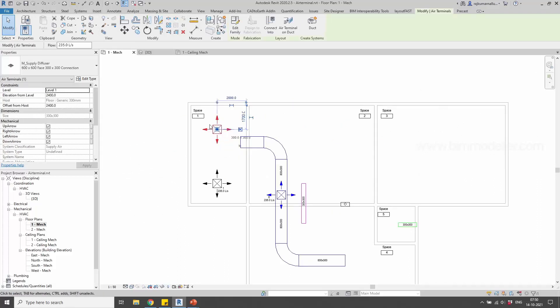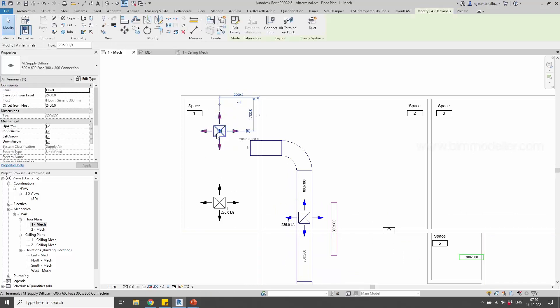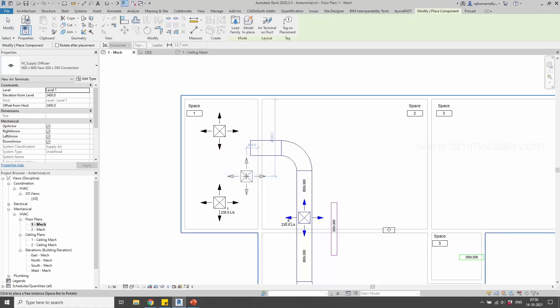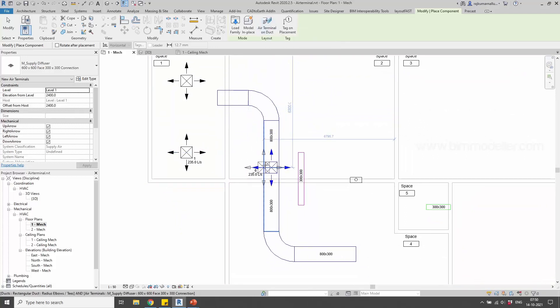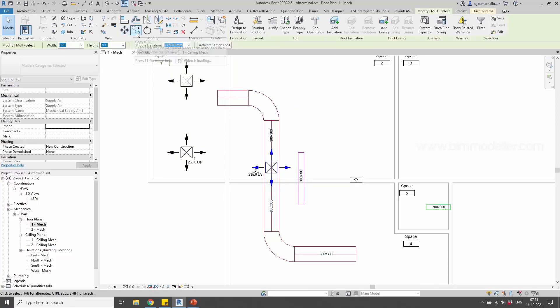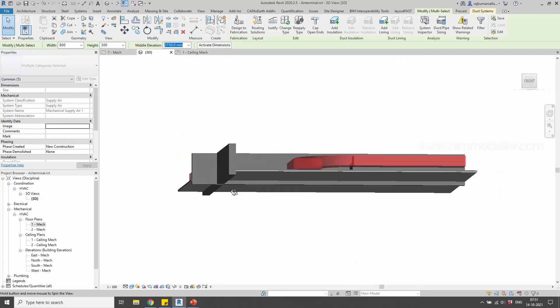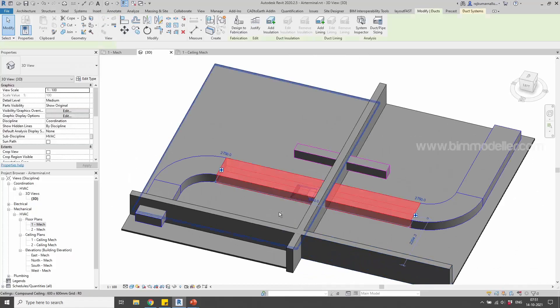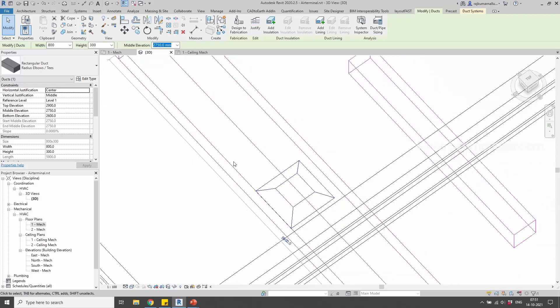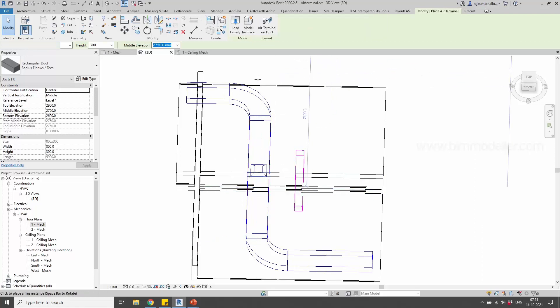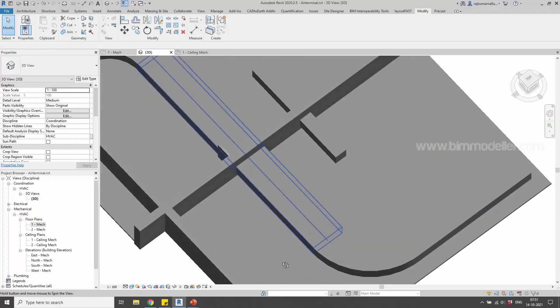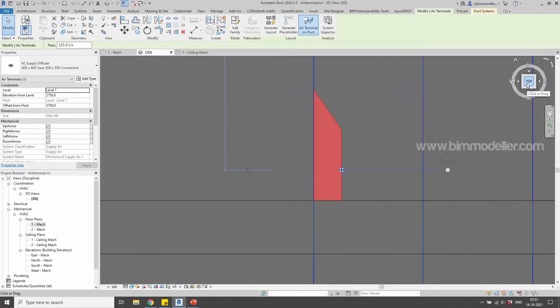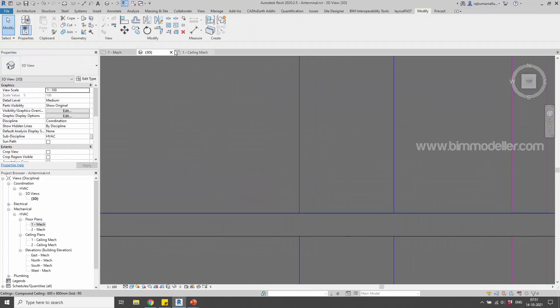When placing air terminals, there are different options available. You can right-click and choose 'Create Similar,' or press CS, so the same element will be created. There is another option — 'Air Terminal on Duct.' If I select the ducts and use the section box in 3D, you'll see an air terminal placed underneath the duct, or you can place them side by side. You can use these options to place a terminal on the side, bottom, or any side of the duct. Usually we place them on the floor plan.